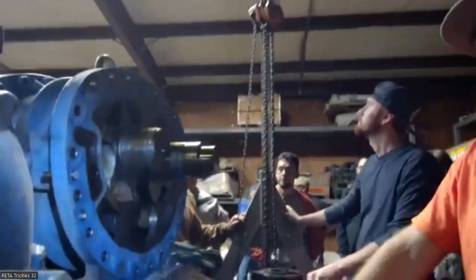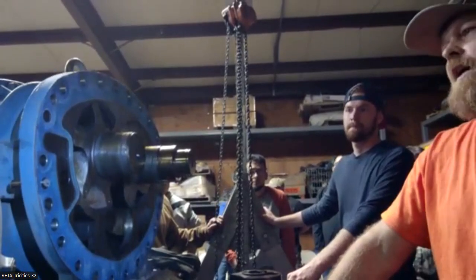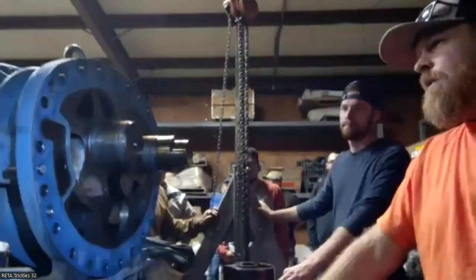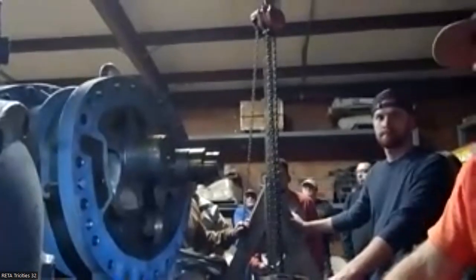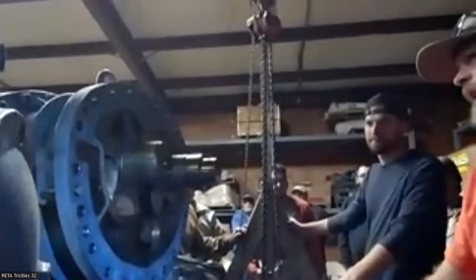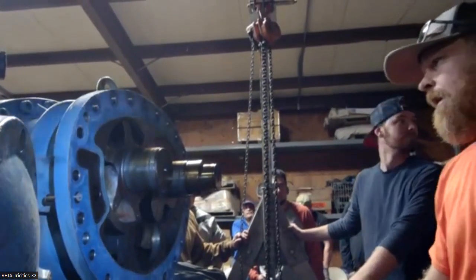How often do you get service reports on a rebuild that you've got in the shop, that tell you this rebuild's been done and this is what's been done to it before? A lot of times there are rebuild tags on them, whether it's from us or other manufacturers. If it's from us, you seem to remember them, especially troubled compressors. Knowing somebody's been in here, you're just mindful of looking at the common components that normally have excessive wear. Has there been any repairs done?